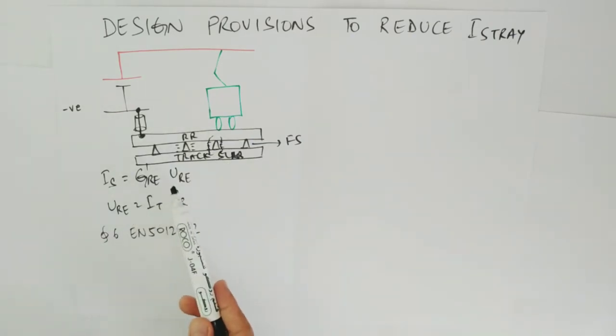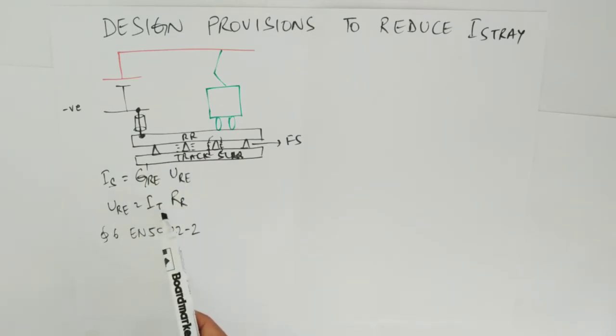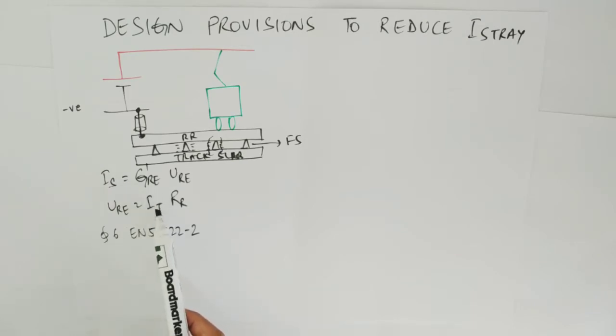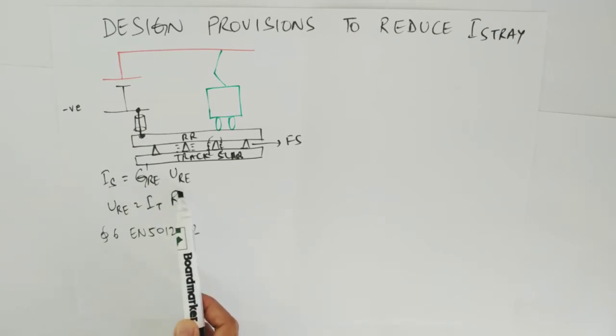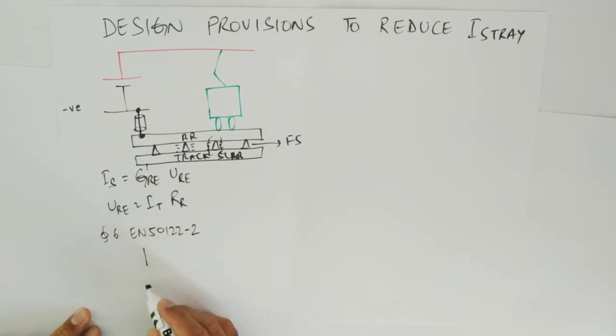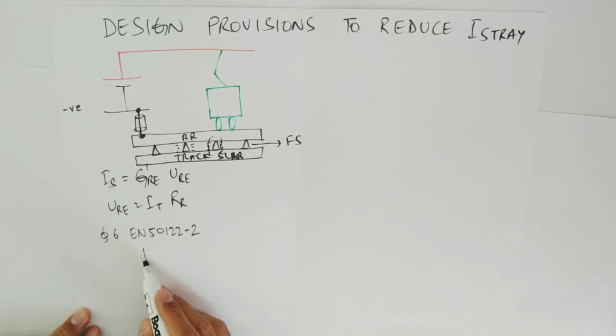Apart from this you can reduce the rail potential — either by decreasing the amount of current, by bringing two substations nearby, or by decreasing or increasing the headway, though these are not preferred. The best method is by decreasing the running rail resistance. This can be achieved by doing exothermic welding between the rail segments instead of providing fish plates.